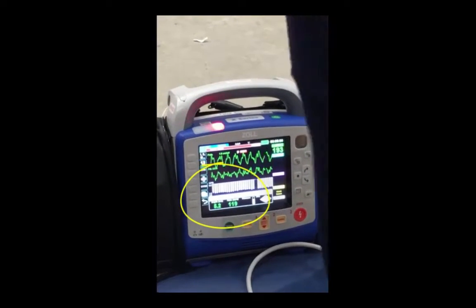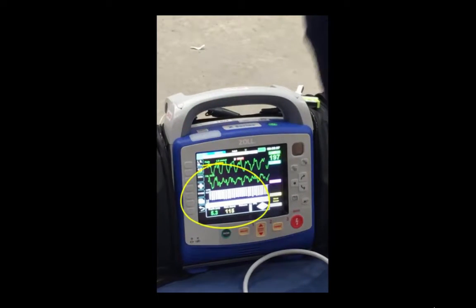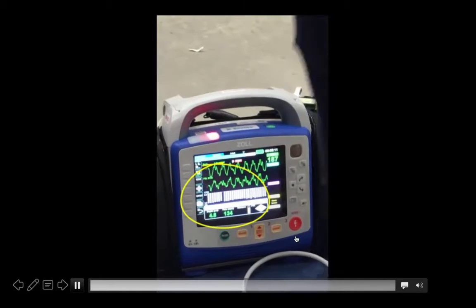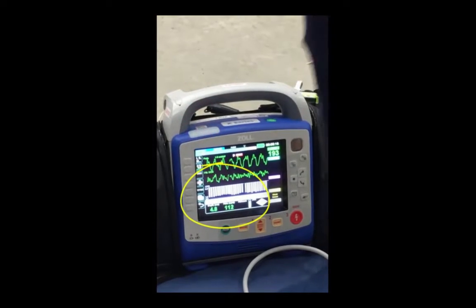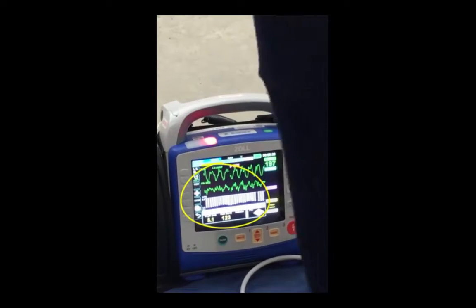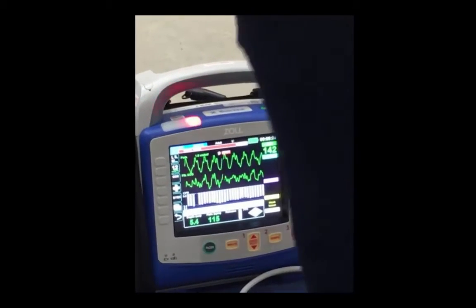As you can see there, really well achieved — right in the middle of the target ranges — and over here in the box is the release, very well too. The CPR feedback has helped maintain effective, quality CPR. The machine also gives some audible prompts, which obviously gives the rescuer reassurance.